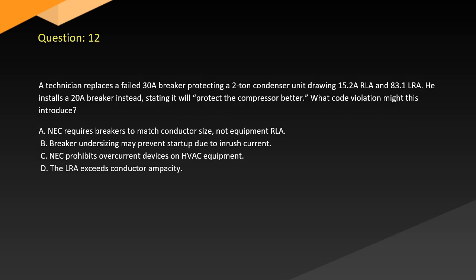Question 12. The technician replaces a failed 30A breaker protecting a 2-ton condenser unit drawing 15.2 RLA and 83.1 LRA. He installs a 20A breaker instead, stating it will protect the compressor better. What code violation might this introduce? A. NEC requires breakers to match conductor size, not equipment RLA. B. Breaker undersizing may prevent startup due to inrush current. C. NEC prohibits overcurrent devices on HVAC equipment. D. The LRA exceeds conductor ampacity.